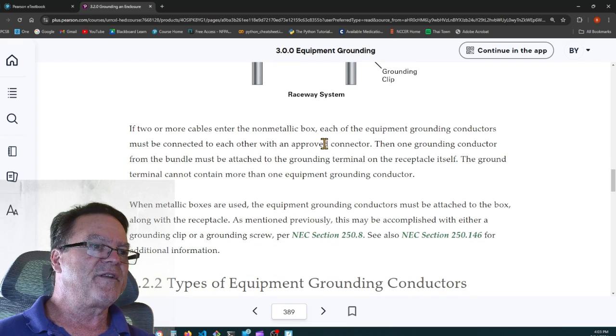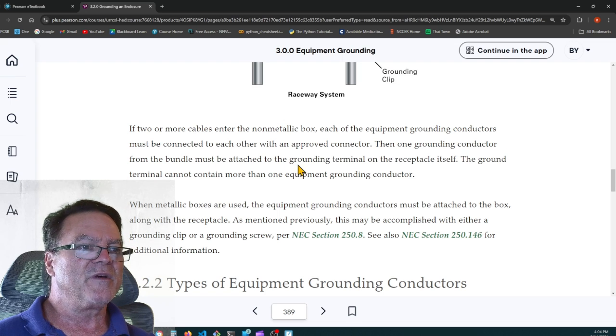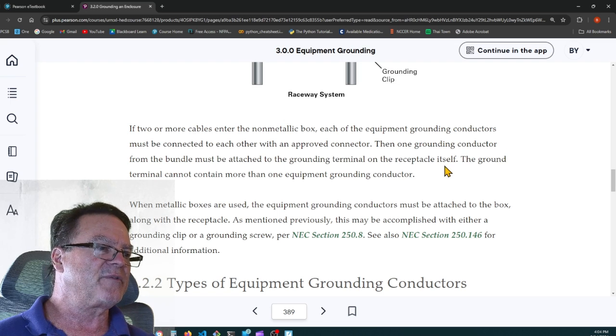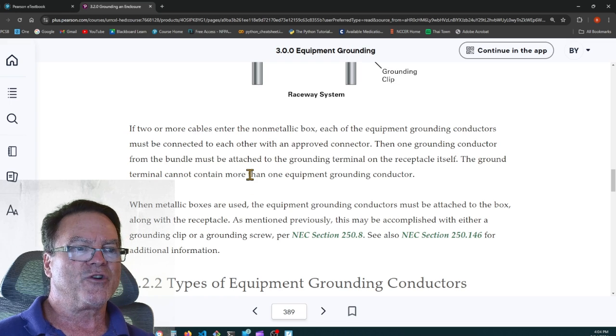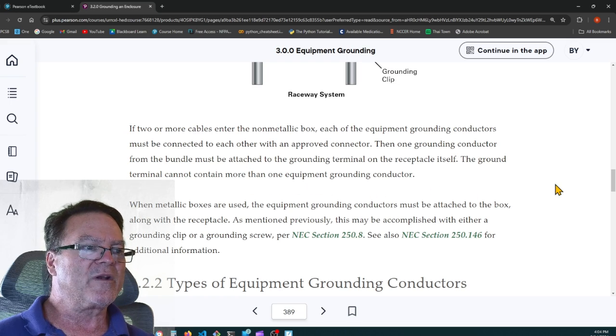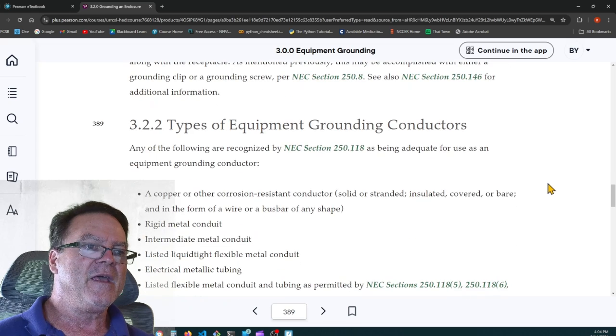If two or more cables enter the non-metallic box, each of the equipment grounding conductors must be connected to each other with an approved connector. Then one of the grounding conductors from the bundle must be attached to the grounding terminal on the receptacle itself. The ground terminal cannot contain more than one equipment grounding conductor. Types of equipment grounding conductors.